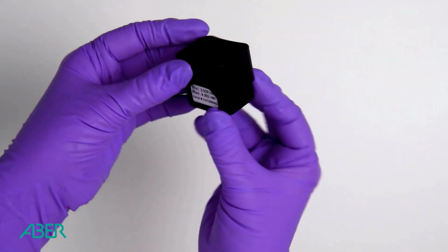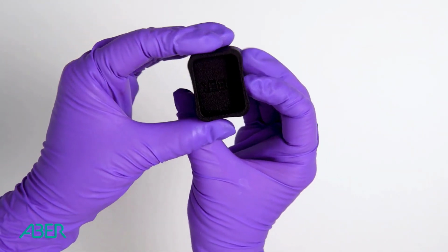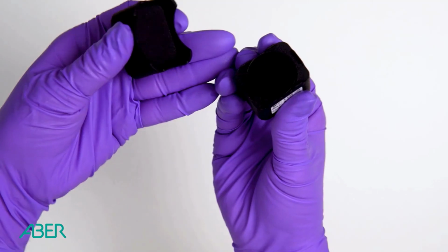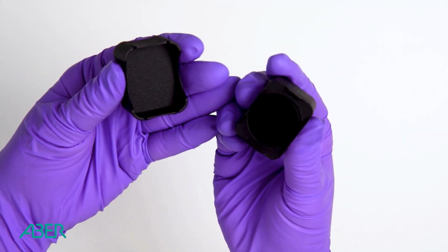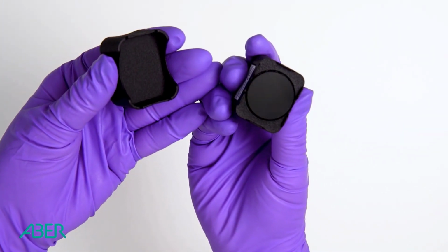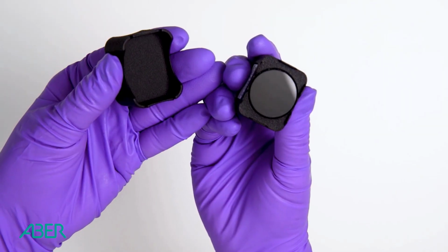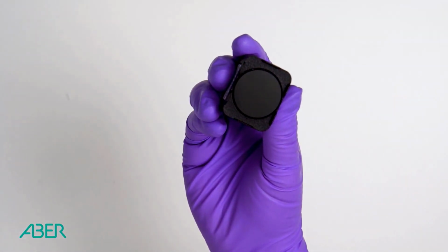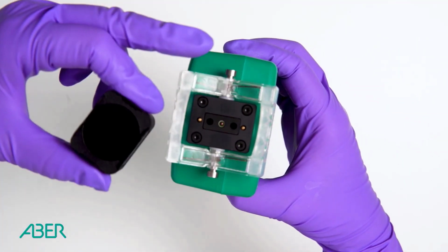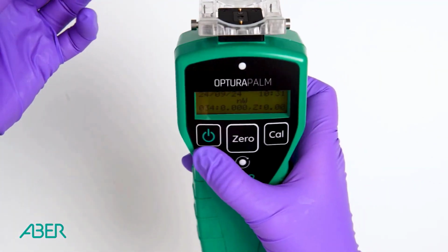Now that you've seen how the palm takes a reading, let's walk through the verification procedure. To use this block, remove the protective lid to expose the surface of the block. This should be inspected before use for any fingerprints, dust or debris. This can be wiped with a lint-free lens wipe. If you need to use IPA, spray that on the wipe first rather than spraying the block. The same advice should be taken to clean the measurement face of the palm.